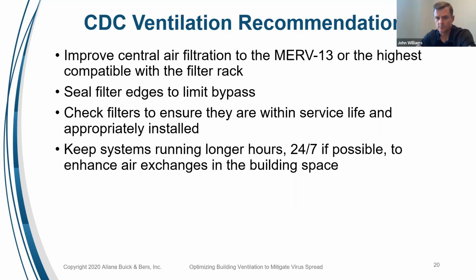So yeah, back to the question about the filters. We have a question here about the filters filtering outside air and not recirculated air. That's kind of an unusual configuration, not to be filtering any recirculated air, especially since this person says that they have steam and chilled water systems. So I'm very curious what's protecting your steam and chilled water coils from recirculated air.